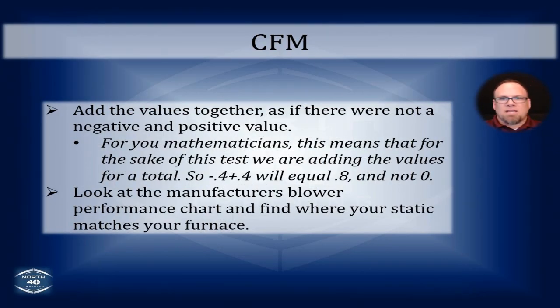Looking at the CFMs, again, when you're taking your CFM static measurements, you're dropping the negative and the positive off and you're adding just the raw number. So like I said, negative 0.4 and positive 0.4, traditionally in mathematics, that would equal zero. But in what we're talking about, you're taking the negative and positive, throwing it on the floor and adding the raw numbers, which would be 0.8 in this particular instance.